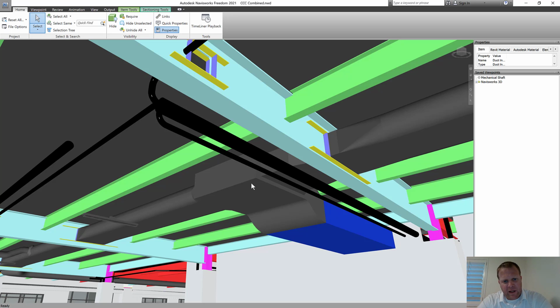We'd be fine if we had sprinklers above this, but I'm not sure exactly where they'd be if it was this high. Maybe they're down below it. In that case, the sprinkler would probably not be higher than that duct, or else it'd be penetrating these beams all over the place. Anyway, it's something to be coordinated, and a lot of times it's up high, that's the point.